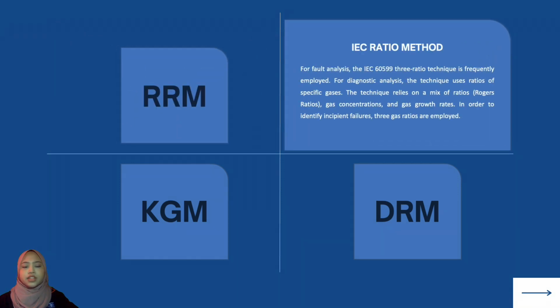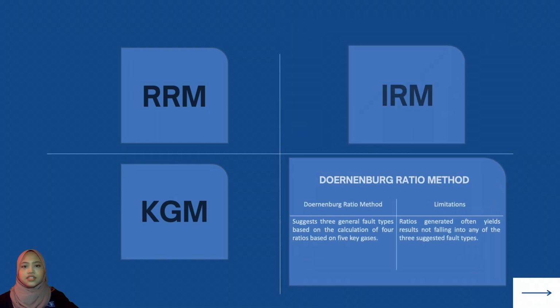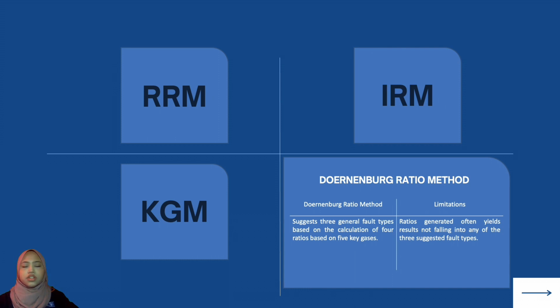Next, the IEC ratio method. For fault analysis, the IEC 60599 ratio technique is frequently employed. For diagnostic analysis, the technique uses ratios for specific gases. The technique relies on a mix of ratios, gas concentrations, and gas growth rates. In order to identify incipient failures, 3 gas ratios are employed. Next is the Doernenburg ratio method. The Doernenburg ratio method suggests 3 general fault types based on the calculation of 4 ratios based on 5 key gases. The limitation is that the ratios generated often yield results not falling into any of the 3 suggested fault types.